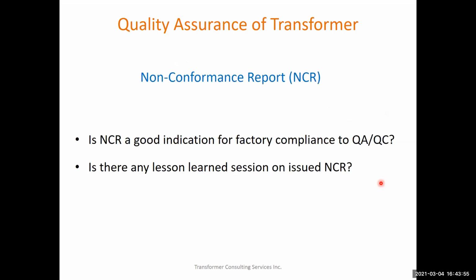I've noticed going around the world that factories are often resistant to issuing any NCR, or non-conformance report. One reason is they think that if they issue too many NCRs, a client seeing them might conclude the factory has a problem. But you should think of it differently: the factory is being serious, issuing NCRs and implementing corrections to improve the quality of the factory and, in turn, the quality of the transformer.